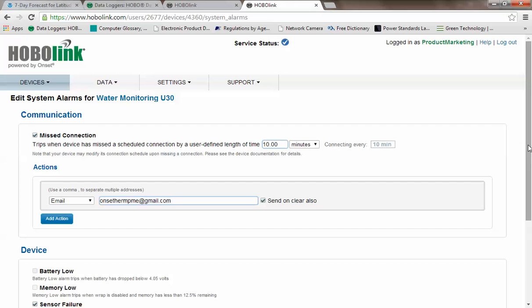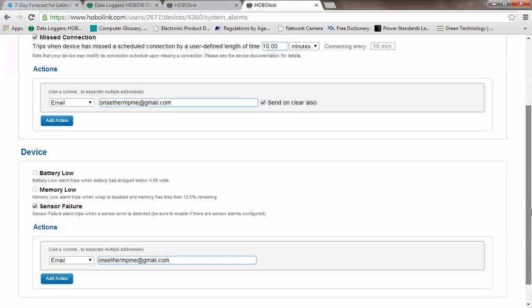The other system alarms that are available are you can be notified if your battery gets low below 4.05 volts, if your memory gets low below 12.5%, or if you get a sensor failure. And again, you can be notified via email or text message.